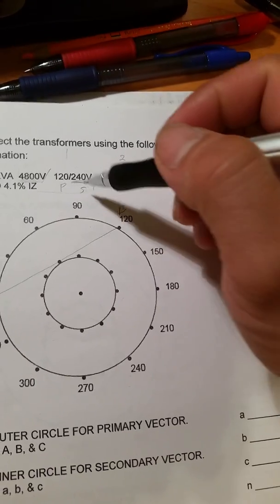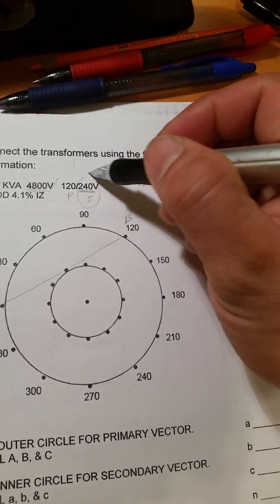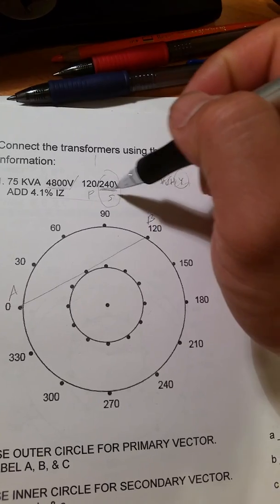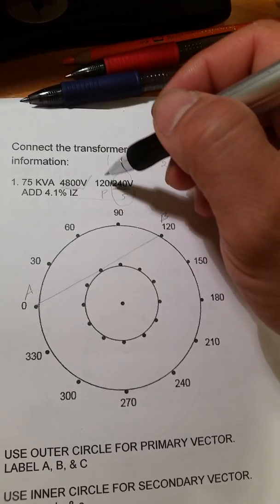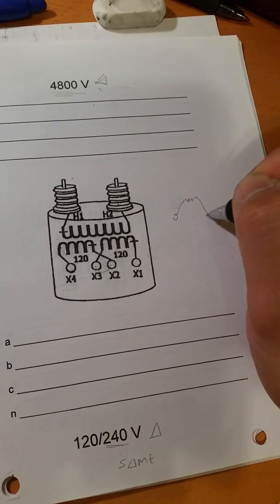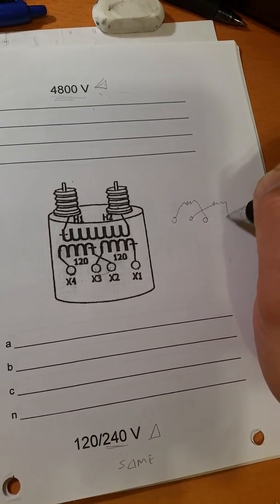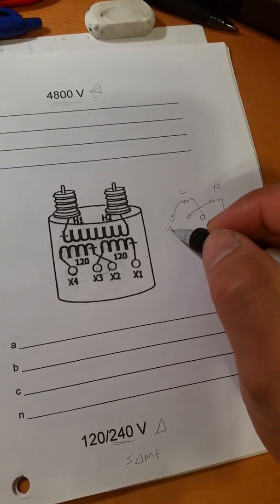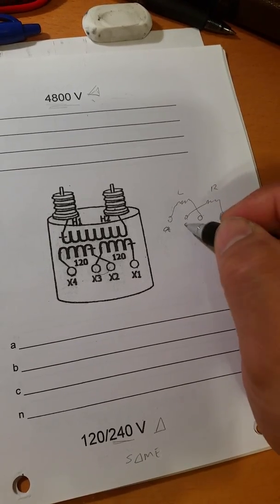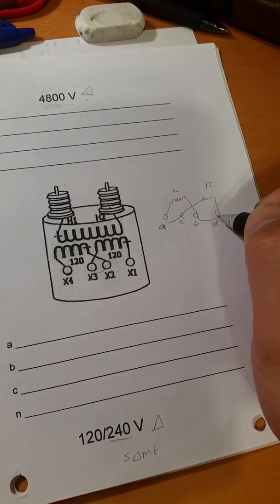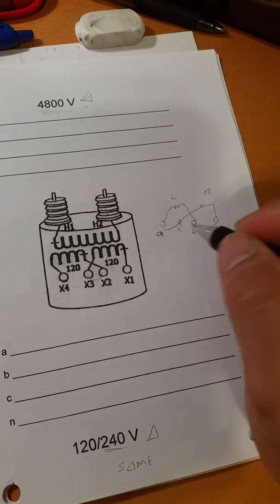So if they're the same, you would series the coils inside. If your second number is not the same, then you'd have to parallel connect the coils inside. In order for you to parallel connect, it looks like this, right? So let's think of this as the left coil and this is your right coil. One coil would be A, B, C, D, right? So if you were to parallel connect it, it would be alley cat, bad dog, right? See how they're in parallel?